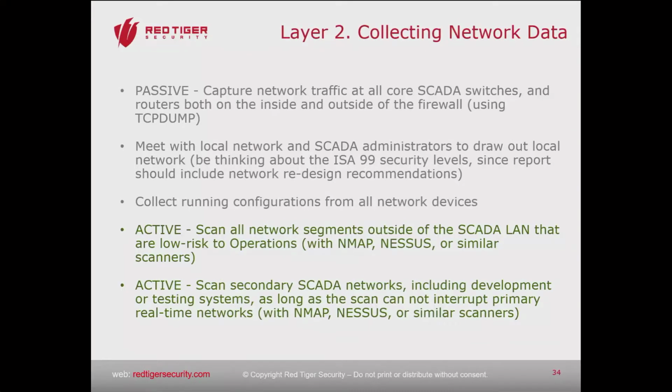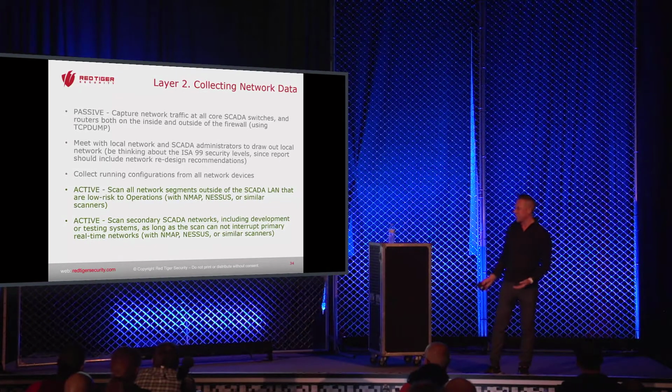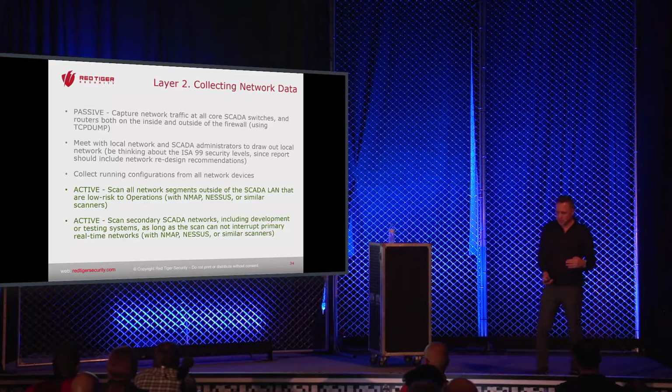Yeah, so we don't suggest that you run Nessus or Nmap or any type of vulnerability scanner on live OT systems, because they can have a potential of causing an embedded device to reboot or come back without its configuration. So everything I'm talking about here is passive tools and a passive mindset.